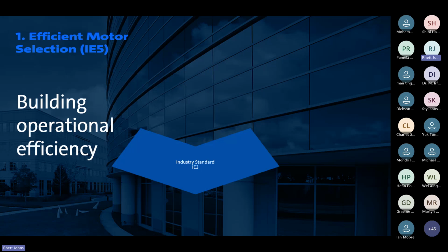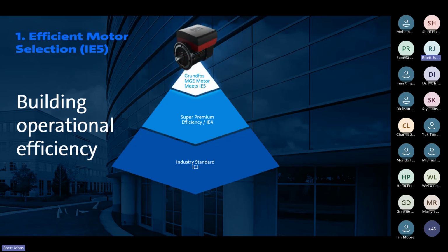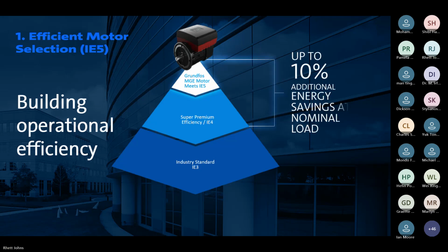The industry standard that we see is IE3, and this is something that you are most likely familiar with as a standard. Super efficiency IE4 also gains efficiency versus the IE3, through more robust stator windings, more copper used than IE3, and in some cases they use permanent magnet motors as well, though less than your full permanent magnet motors. And then the final top tier that you get is an IE5 motor. So an IE5 motor is the highest standard that you can get currently qualified within industry, and you can get up to 10% additional energy savings just by converting to a permanent magnet motor that has the IE5 efficiency standard.